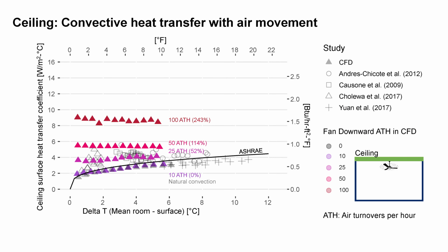And recent laboratory studies also show comparable results with the ASHRAE guidelines for the most part. Our natural convection case using CFD also shows pretty comparable results, and also the 10 air turnovers per hour. Here we're using the term ATH to signify how much airflow the ceiling fan is recirculating in the air. So it's not an air exchange, it's just a recirculation term here, just to be clear.